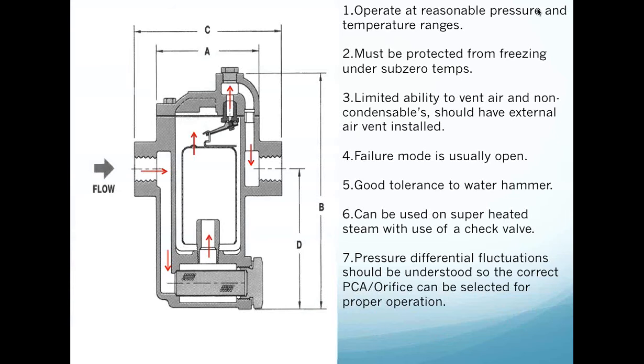The first trap we're going to look at today is an inverted bucket steam trap. And if you can follow my arrow, I have some red arrows. The one thing I want you to know about these traps is they are very good devices. They have a long history. They have worked very successfully for many years, and they are a good device. But like any trap, you have to understand how they are built, how they function, and make sure that you understand the actual pressure differential that these traps will be subjected to.